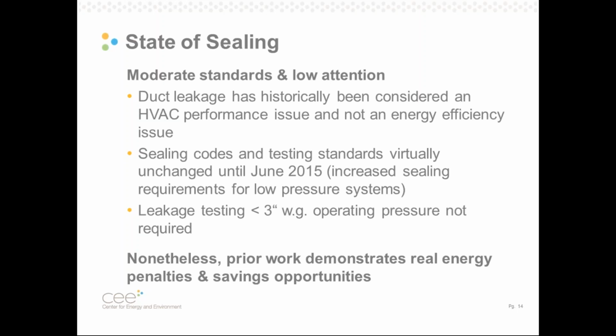Here I just want to set the ground briefly so that we have a starting point to talk about duct leakage. So historically and still commonly today, duct leakage is not considered an energy efficiency issue. It's mainly a performance issue. Consequently, when a duct system gets built, if it has a lot of duct leakage, that's generally overcome with more fan power.